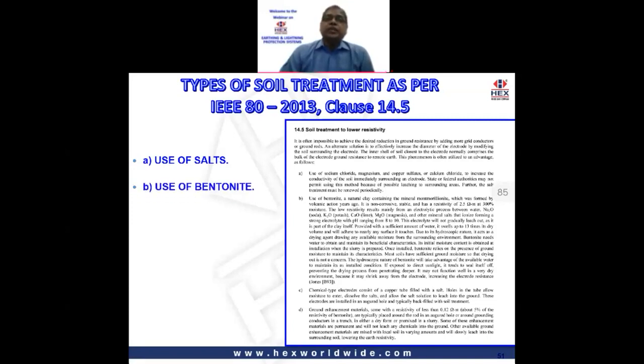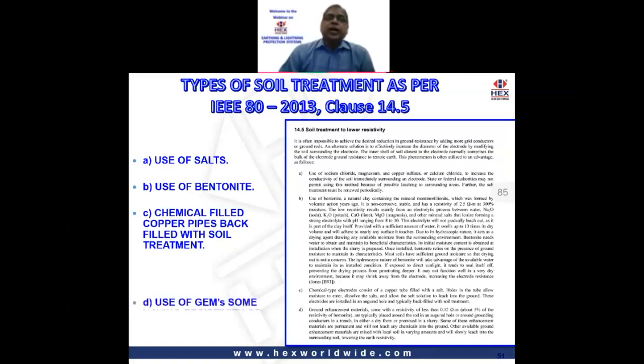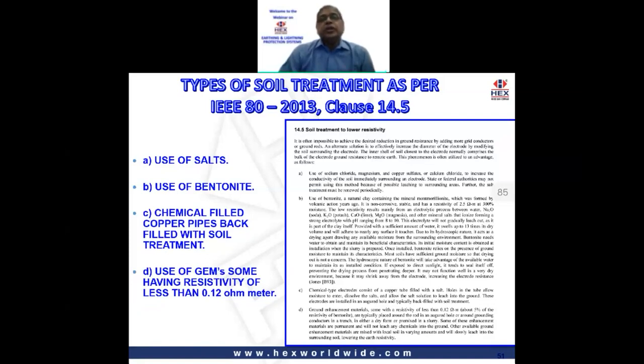Now subclause B states that bentonite can be used. This also has its disadvantages as it needs water to maintain its reliable characteristics. Subclause C states that chemical filled pipes with holes to allow the chemicals to leach out can be used along with treatment of the soil surrounding the electrode. And subclause D states that ground enhancement materials with various values of self-resistivity can be used to improve the soil surrounding the electrode. Now these are what are called maintenance-free earthings.